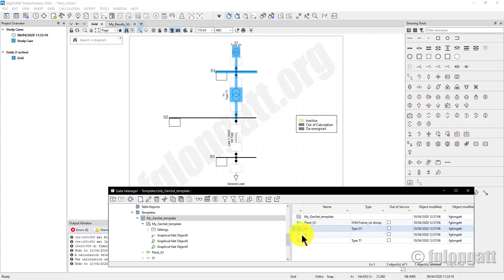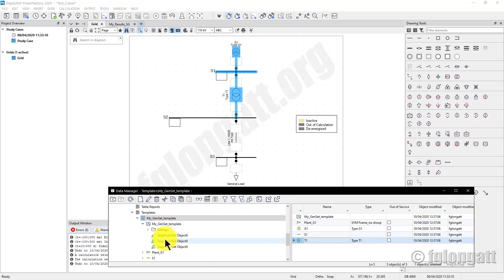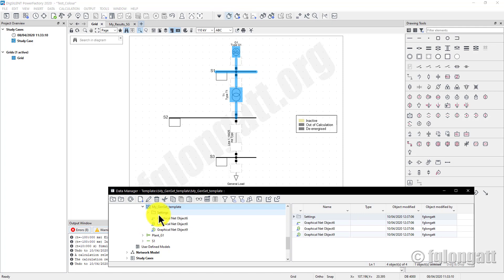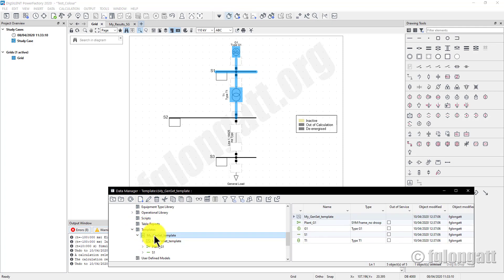Inside the template you have the generator, the busbar, and the transformer. Note that the transformer has only one side connected — the high-voltage side. Many people try to create this manually by placing the composite model, the busbar, and the generator, but if the graphical information is missing you will have no graphical representation inside the grid model. One of the things PowerFactory does automatically when you define the template is include those graphical objects for the network elements, as well as the result settings.